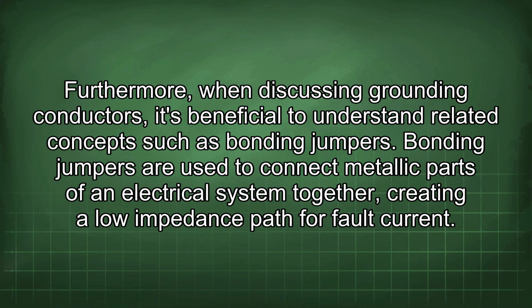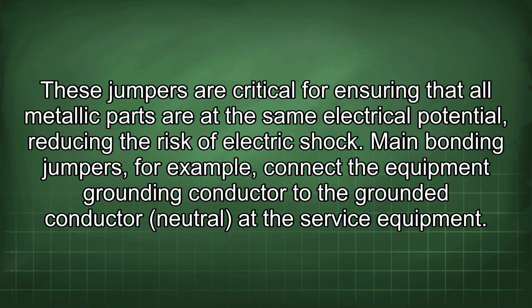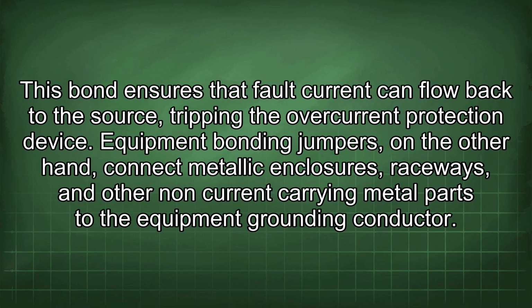Furthermore, when discussing grounding conductors, it's beneficial to understand related concepts such as bonding jumpers. Bonding jumpers are used to connect metallic parts of an electrical system together, creating a low impedance path for fault current. These jumpers are critical for ensuring that all metallic parts are at the same electrical potential, reducing the risk of electric shock. Main bonding jumpers, for example, connect the equipment grounding conductor to the grounded conductor (neutral) at the service equipment. This bond ensures that fault current can flow back to the source, tripping the overcurrent protection device.